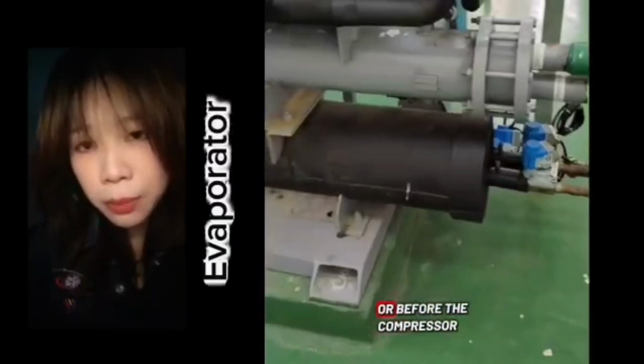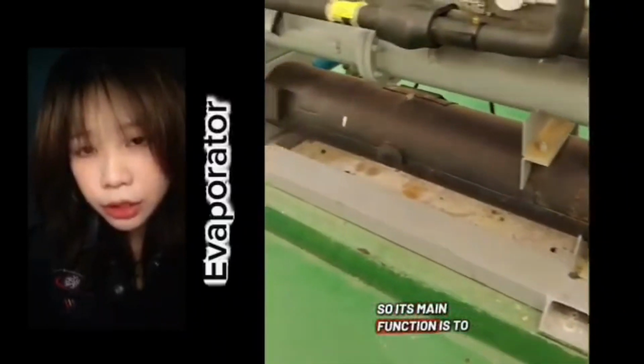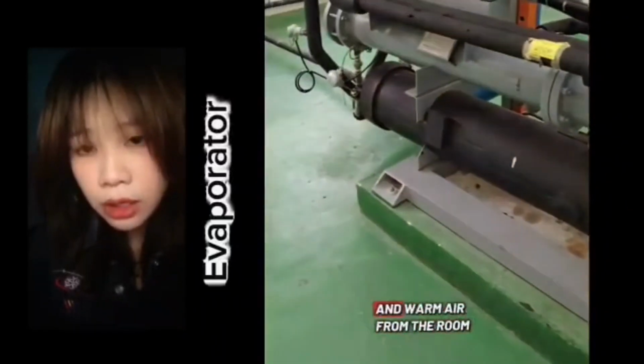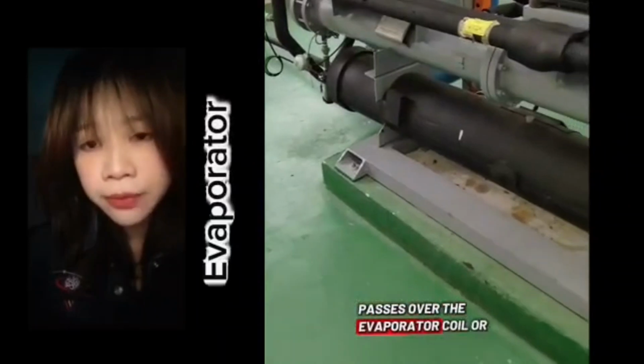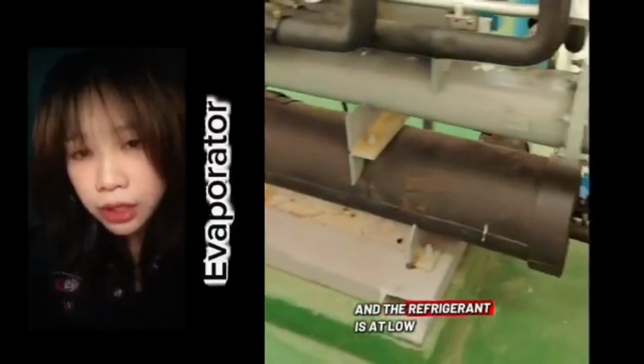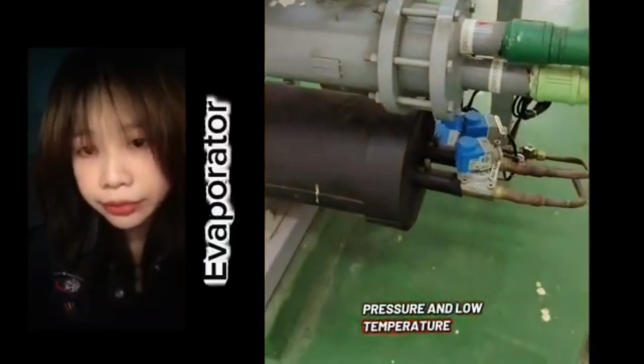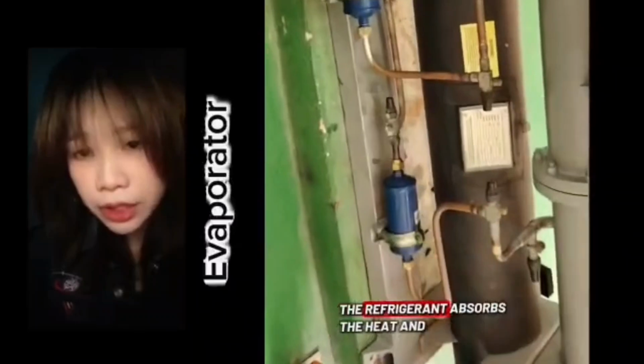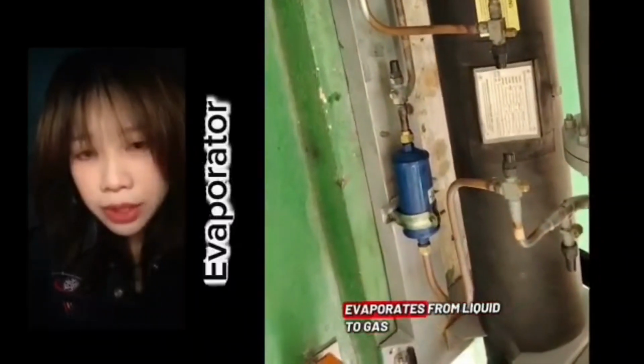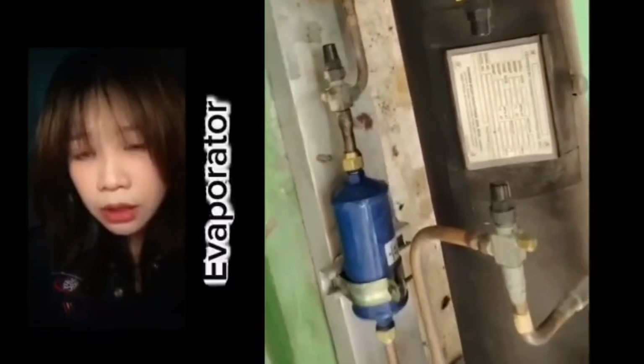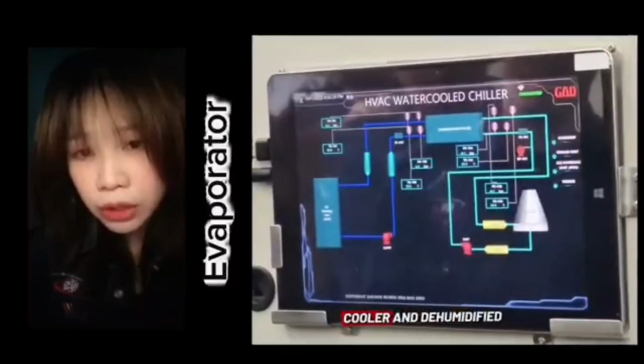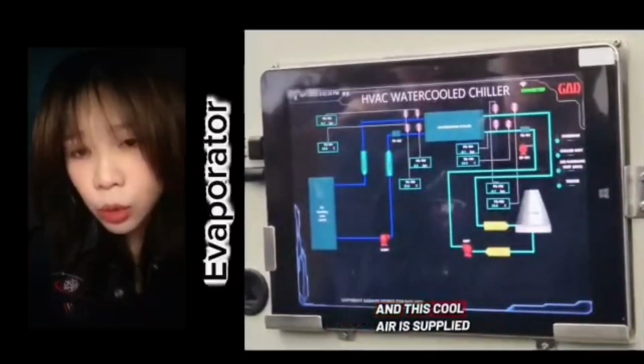So the evaporator is usually located after the expansion valve or before the compressor. Its main function is to absorb heat from the indoor air. Warm air from the room passes over the evaporator coil, and the refrigerant inside is at low pressure and low temperature.